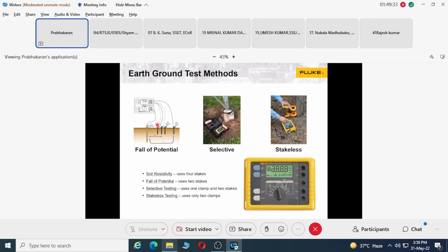Many times when you use low end instruments, I've seen at many customer places they use some 10,000 rupee devices which always give the right reading. This is actually misleading, and they don't know what mistake they are making. When you always get the right reading in earthing, you can be sure the instrument is faulty. I have proven this at least in half a dozen customer locations where I demonstrated it, and that's why I'm very confidently telling this.